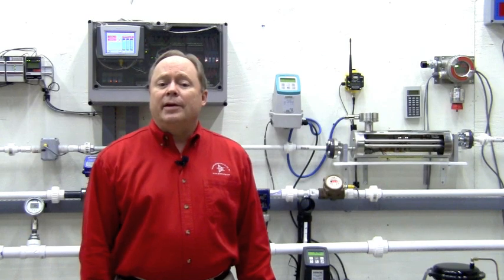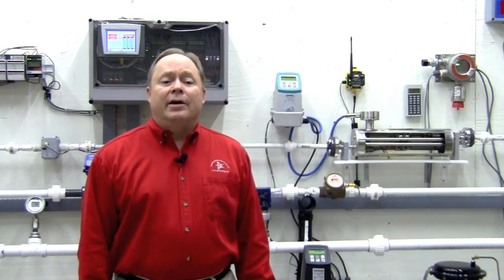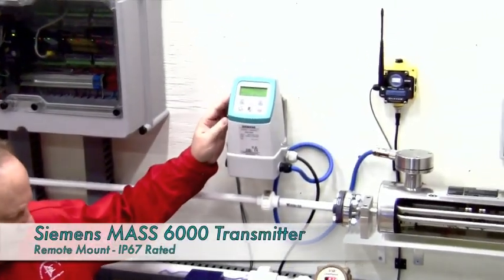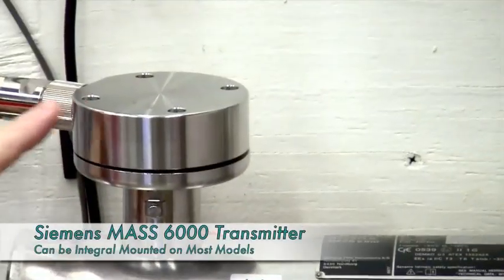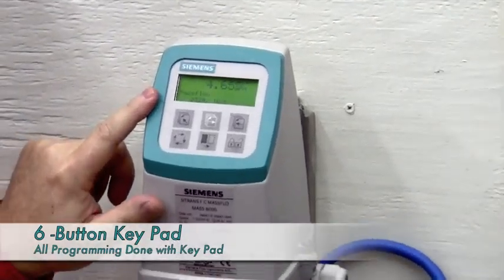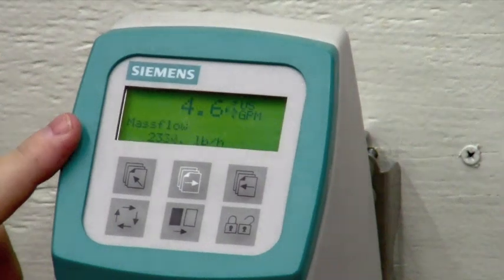I'm going to concentrate on the MASS 6000 transmitter and the MASS 2100 meter, which we have installed in our flow lab. It's a cutaway version, so we'll be able to show the internals of the meter. Let's start with the transmitter. Here in the lab, we have the transmitter remote mounted — it can also be mounted directly to the 2100. All the configuration can be done with this six-button keypad. It is a straightforward menu structure with advanced diagnostics and service sections for troubleshooting.